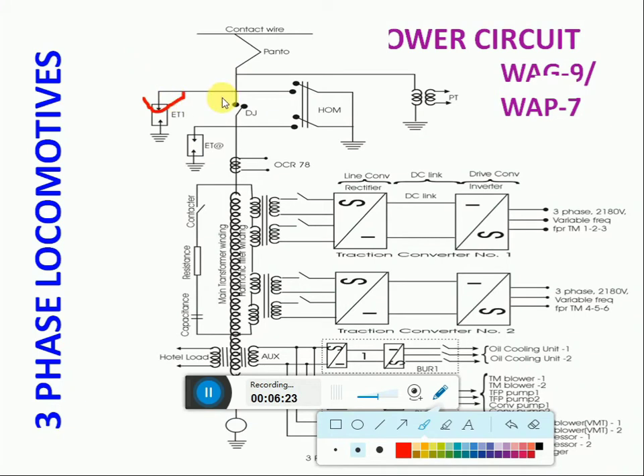ET1 is connected before VCB and ET2 is connected after VCB. Any surge voltages before VCB closing will be grounded through ET1; any surge voltages after closing of VCB will be grounded through ET2. The HOM is a grounding switch used for climbing on the loco roof to attend any problem. We have to inform TPC, PRD staff will come, they will take the power block, and we have to secure the loco and ground it along with PRD staff.